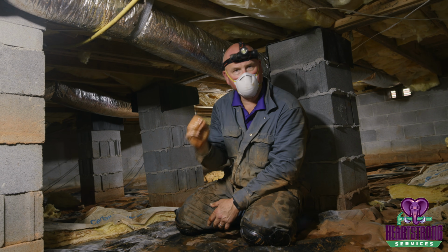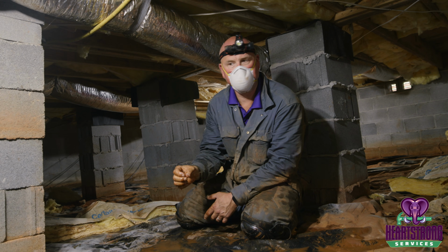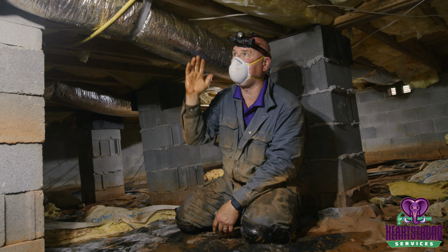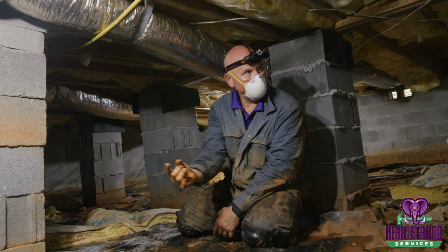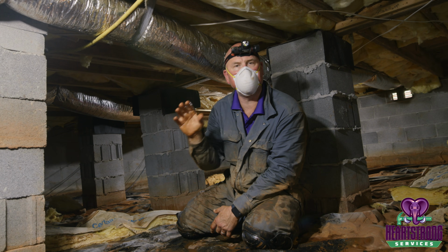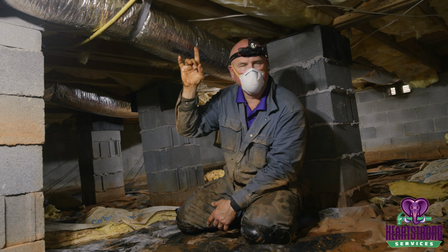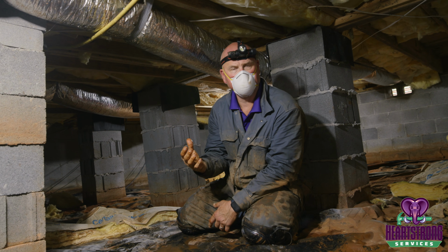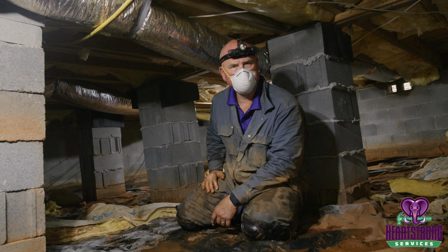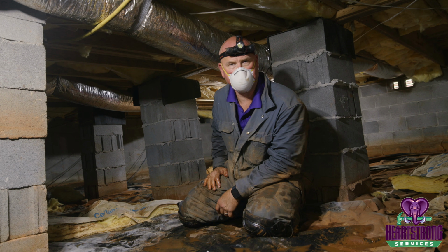Whether you choose to do a soda blast to remove the fungus, or you do an actual cleaning with a hydrogen peroxide treatment, or whatever you choose, the wood moisture content is too high. It's too wet. You can't come down here and clean it and do it properly. So we have a technician come out and temporarily block up all the vents and direct air exchange and install a temporary dehumidifier so that we can lower the relative humidity and reduce the wood moisture content to prepare this environment to be properly treated for the fungus and also to stop the ductwork from sweating, so that when we get to the final touches, we don't have water that's just raining and dripping all over top of the project.